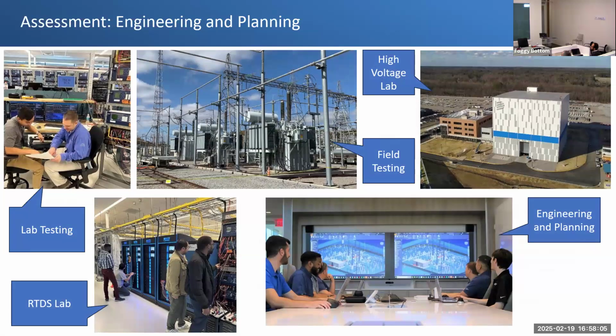So what are some of the things we're doing? We lean in heavily on lab testing. This is the only energized 500 kV geomagnetic current injection testing ever done in this country, in this hemisphere, at our Carson substation. We took energized transformers and ran 1,500 amps of DC into the neutral of that transformer to see how it performs on the grid. We got great measurements from that.